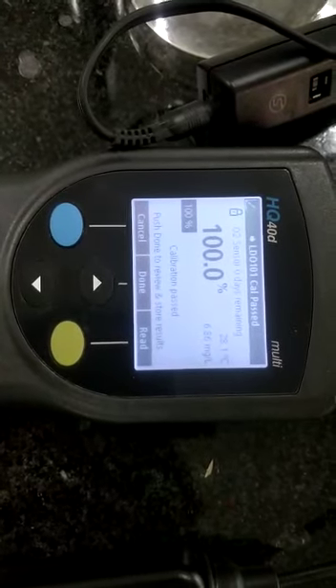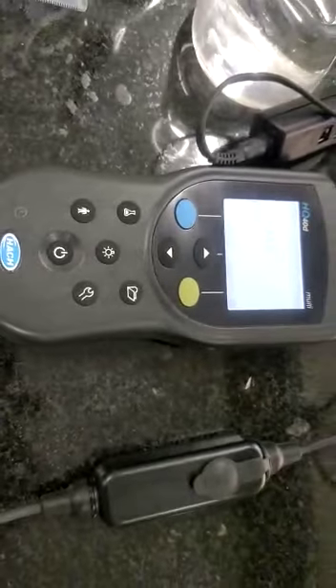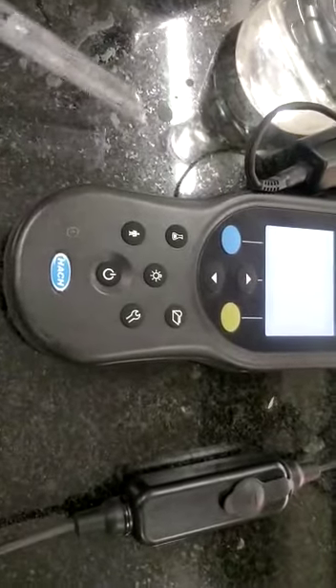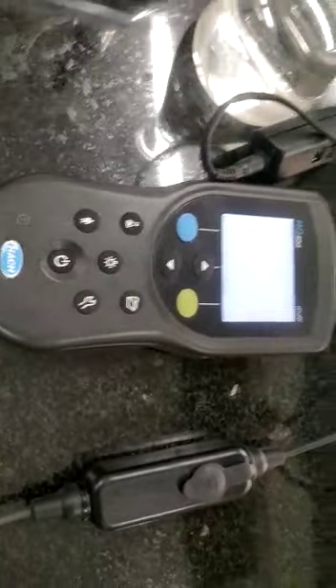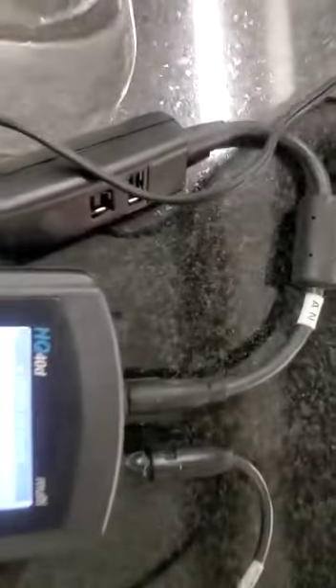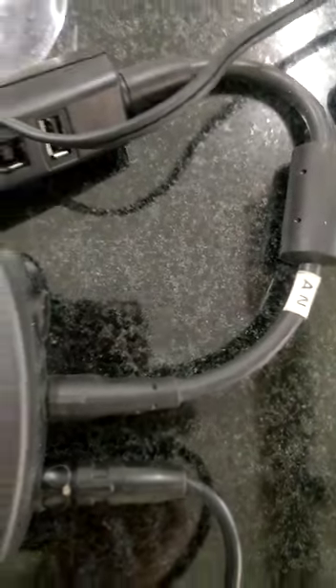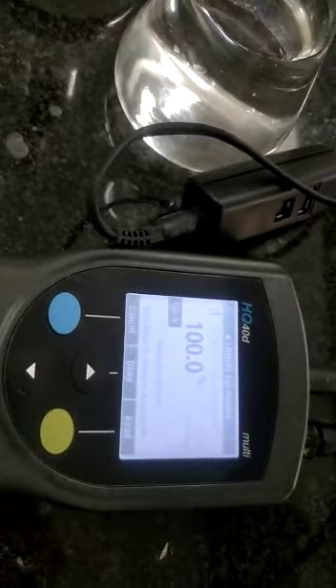Now, you should take different precautionary measures while working with this instrument. Firstly, all the probes should be connected tightly. There should be no air bubble present in the sample. The sample should be checked for DO as soon as it is collected from the site. Thank you.